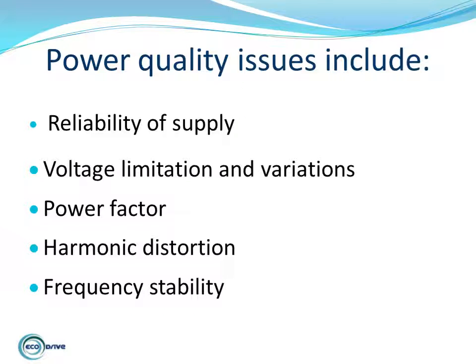Power quality issues include reliability of supply, voltage limitations and variations, power factor, harmonic distortion and frequency stability. Power quality issues are further being challenged by embedded generation such as grid-connected PV systems. The aim of the initial generous feed-in tariff for grid-connected PV systems was to encourage investment in renewable energy and to aid Australia in reaching the mandatory renewable energy target. South Australia, Queensland and Western Australia have seen the greatest uptake of PV grid-connected systems.